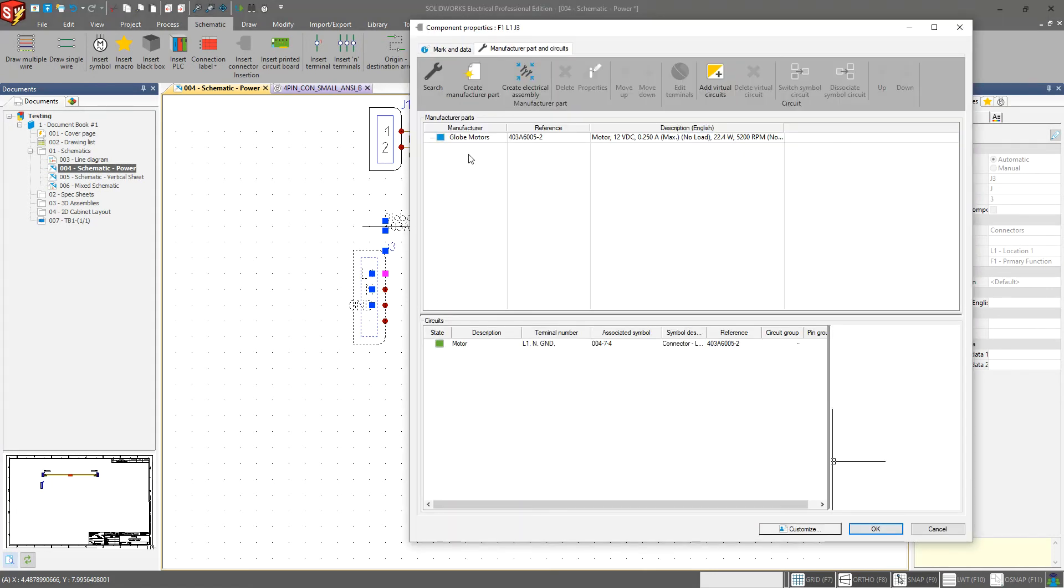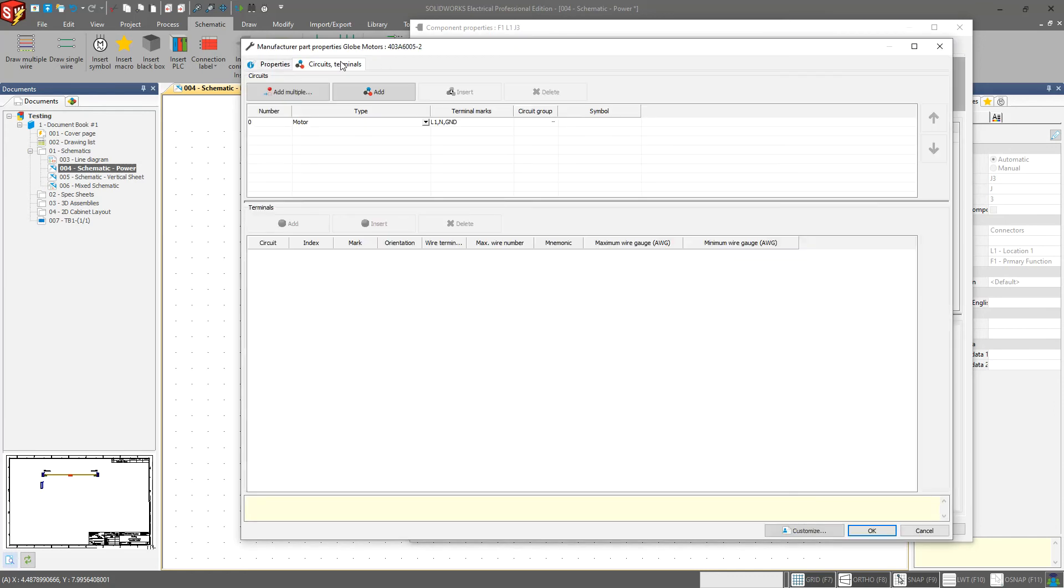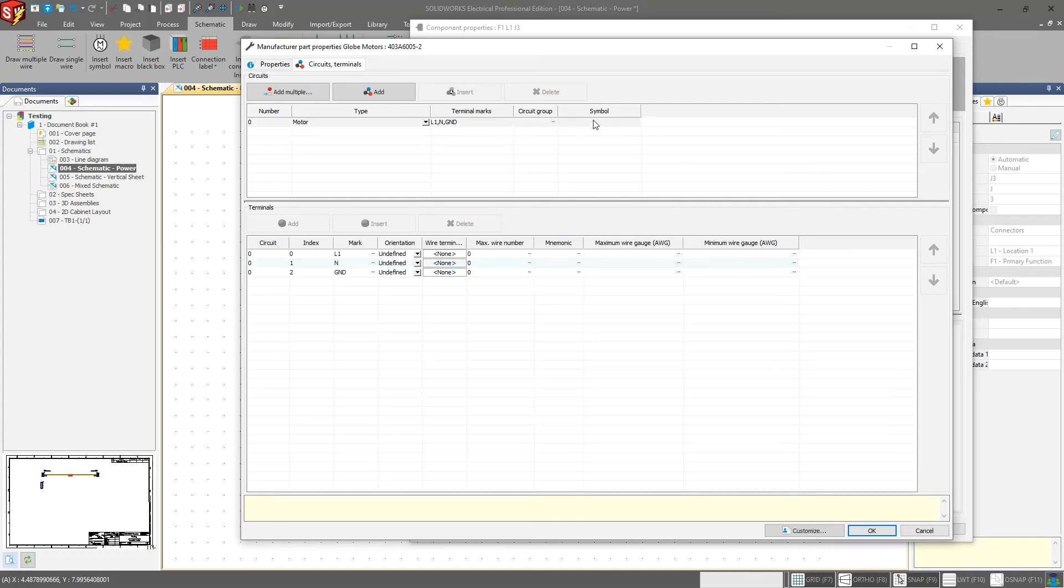It doesn't mean that I can't still go ahead and select that. It just will not automatically connect them. So again, it's just built into the software that it recognizes that these are two different types of circuits. The manufacturer part and the symbol information are different. So it's not going to automatically make that connection. Now I can override that. I can just simply take this and drag that over the top and say, yeah, I want it to be that. And now when I select this pin four of the symbol is pretty much ignored because there was no circuit information. There was no terminal information for pin four in that manufacturer part. We do get our line, one neutral and ground from that motor information there.